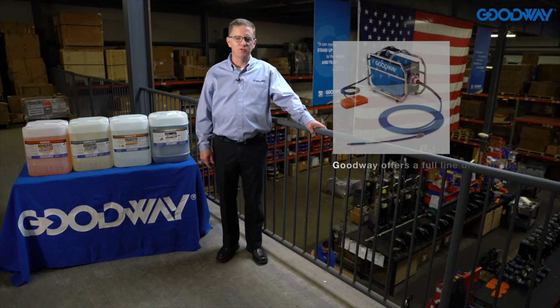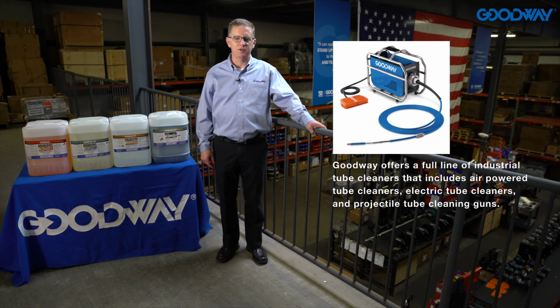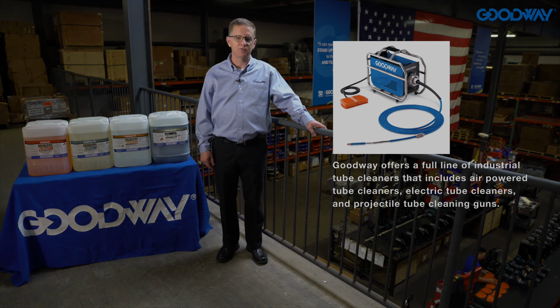Our solutions range from our scale break family of descalers to not only our brush systems, but also our tube shot systems. Mechanically removing a deposit would come into play when there's a very complex one that our chemicals will not dissolve. For instance, a silica or a phosphate deposit. In a situation such as that, the mechanical means are going to be more successful.